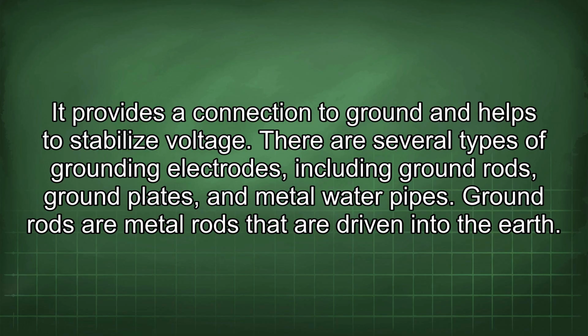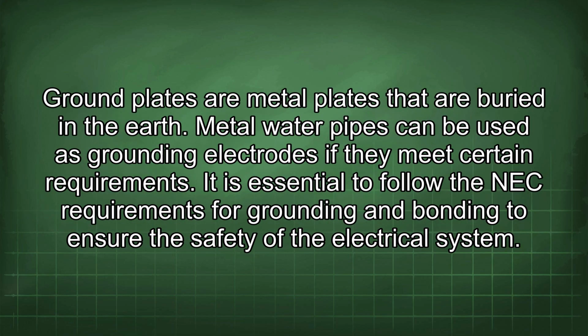There are several types of grounding electrodes, including ground rods, ground plates, and metal water pipes. Ground rods are metal rods that are driven into the earth. Ground plates are metal plates that are buried in the earth. Metal water pipes can be used as grounding electrodes if they meet certain requirements. It is essential to follow the NEC requirements for grounding and bonding to ensure the safety of the electrical system.